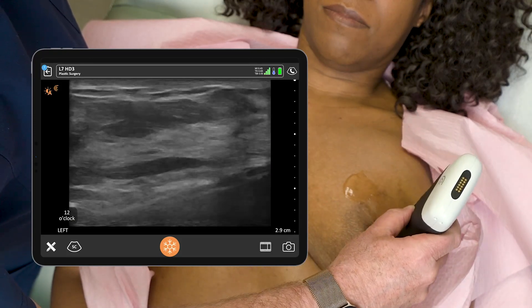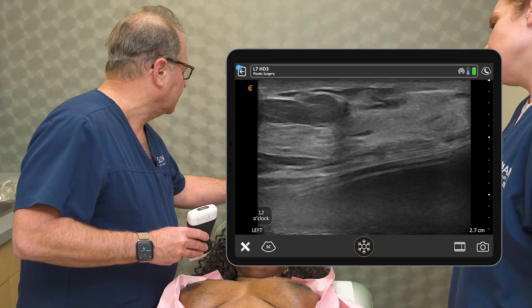The wireless device is way better if you use it intraoperatively. It's so much easier to put it in a sterile condom for doing BBL or any type of targeted fat grafting than having a cable draped all over the bed, with you stuck in a fixed position relative to whatever display you're viewing — whether it's an iPad, iPhone, or a computer on a cart. With this device, the iPad is just on a little stand so I can look left or right. It's so much easier being wireless, and you don't have to worry about wire length. Competitors' devices have wires that are just too short to keep the display in the right spot.